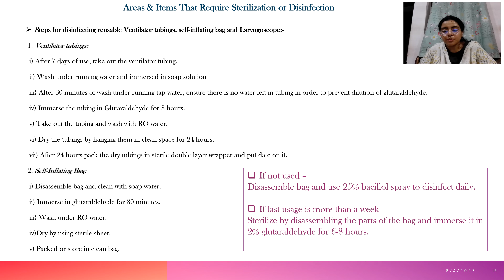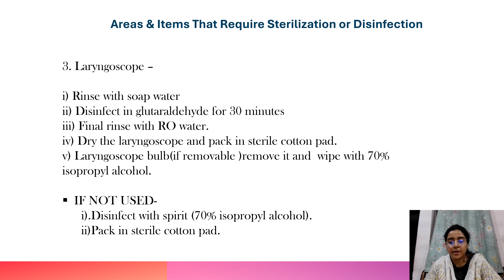Further, moving ahead with laryngoscope disinfection. Rinse it with soap and water. Disinfect in glutaraldehyde for 30 minutes. Final rinse with RO water. Dry the laryngoscope and pack in a sterile cotton bag. Laryngoscope bulb, if removable, remove it and wipe with 70% isopropyl alcohol. If it is not in usage, then disinfect with 70% isopropyl alcohol and pack in a sterile cotton bag.